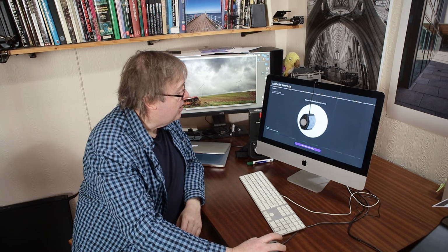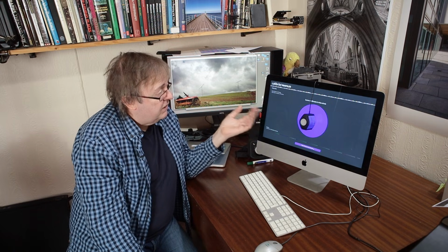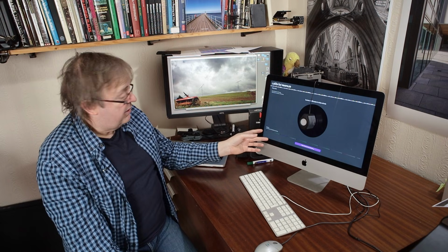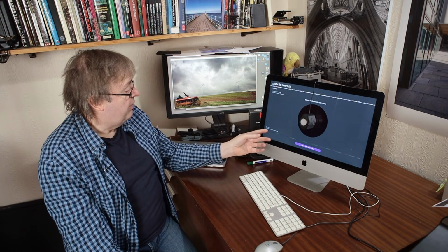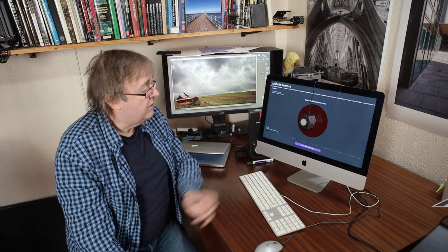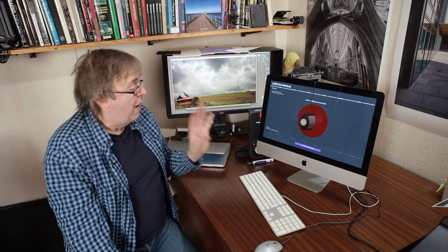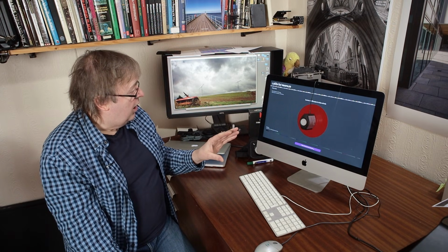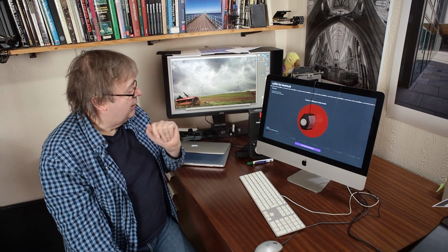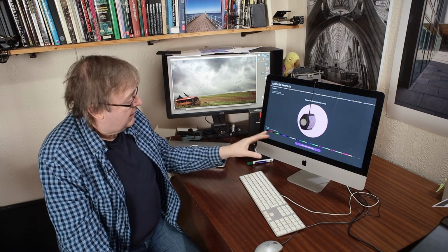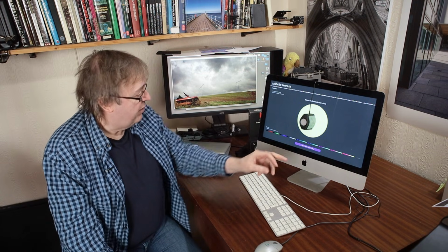So let's start the measurement, and this is now going to run through all the coloured patches. Now it starts here, and this will go on for a few minutes, and it's telling me that 210 of 211 remaining. Well, it's going through relatively slowly on this. I'm not going to subject you to the whole lot. We'll just jump forward until it's done. A few minutes have passed by, and you can see there's a progress bar runs along the bottom here. Tells me I've only got a few more patches. We've got about 10 patches left.